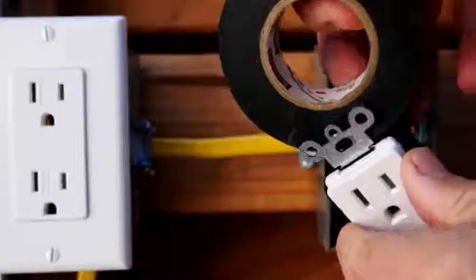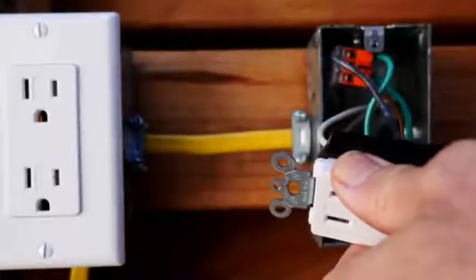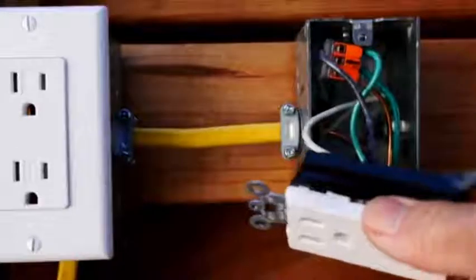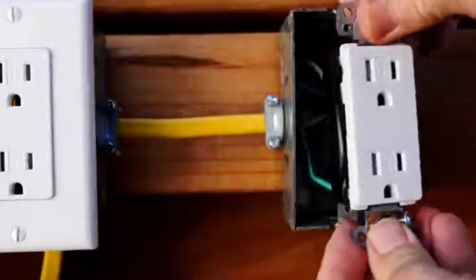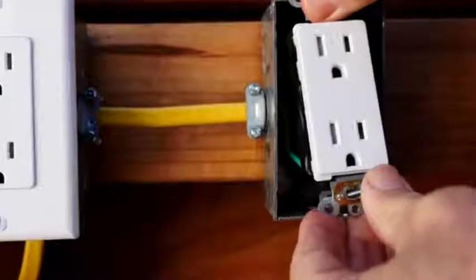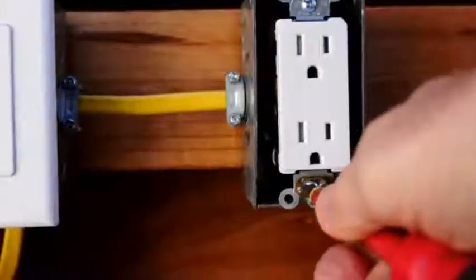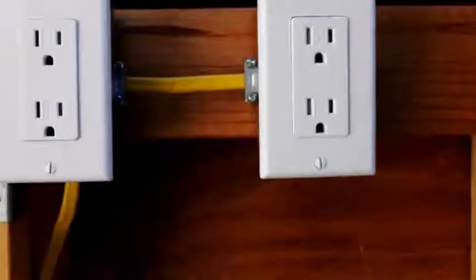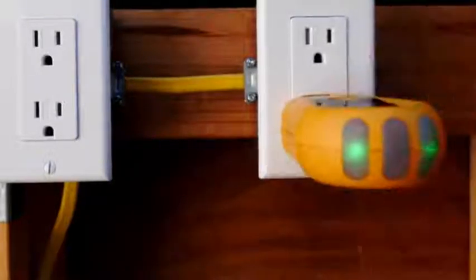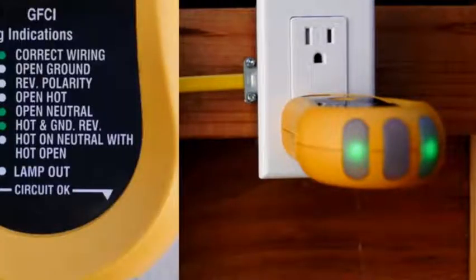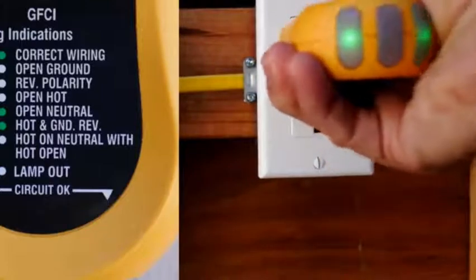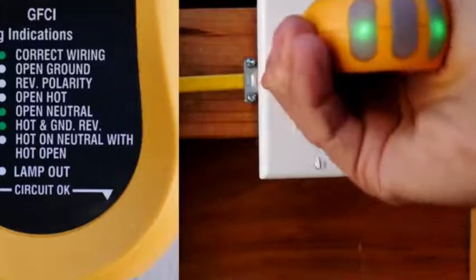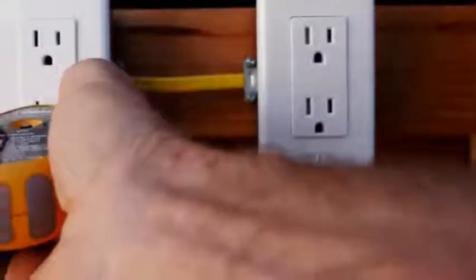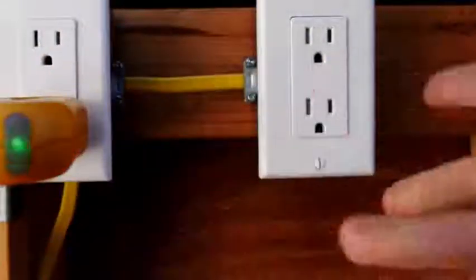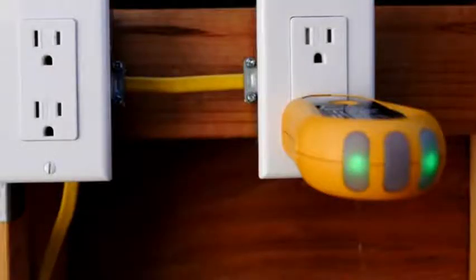Now I'll put a couple wraps of black electrician's tape around the receptacle for safety. Dress the wires, that is, put the appropriate bends in them to make them go in more easily. Tighten up the receptacle and put on the wall plate. Now I've turned back on the circuit breaker, and we're going to test out the receptacle. We see there are 2 green lights, which means correctly wired. And we can check out the other outlet of the receptacle, and we can check out other receptacles on the circuit as well. And we see everything's great. So that's how you fix the dangerous situation of reversed polarity.